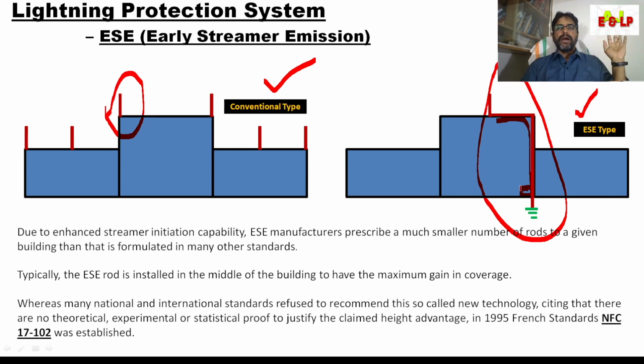Never. Actually, for a building or a house, we can do the lightning protection with 20,000 or 30,000 amount. But if you are going to ESE, it will be around 1 lakh. So never think that the expense is very low in ESE. It is not there.